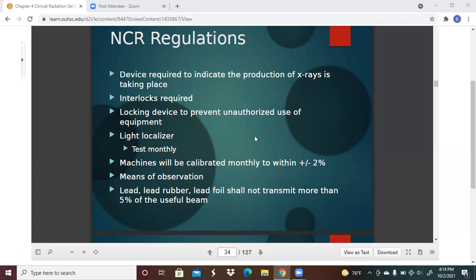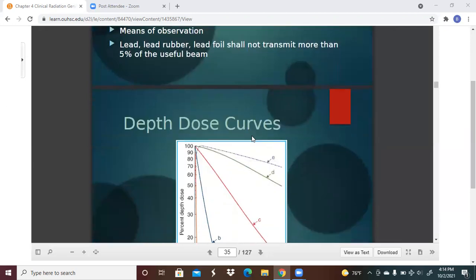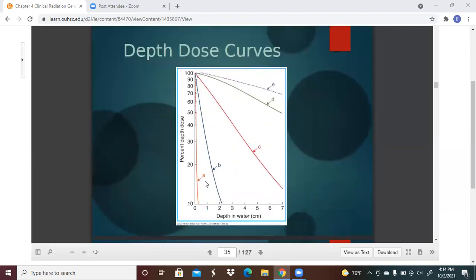The device is required to indicate that the production of X-rays is taking place. Interlocks are required. There must be a locking device to prevent unauthorized use of the equipment. It's supposed to be tested monthly. Machines will be calibrated monthly to within plus or minus 2%. You've got to have a means of observation, and lead rubber or lead foil shall not transmit more than 5% of the useful beam. So you can see the depth dose curves right here in front of you.